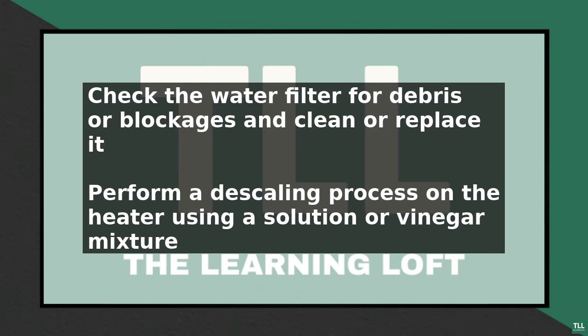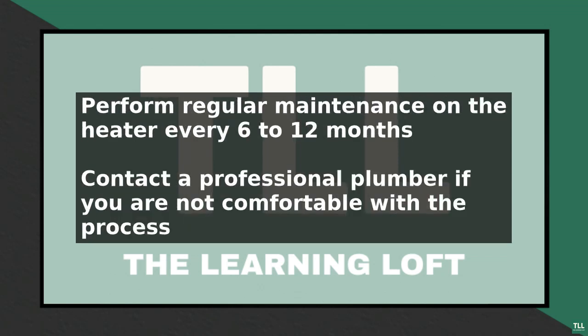It is essential to perform regular maintenance on your Rinnai Tankless water heater to prevent scaling issues. Check the water filter regularly and perform a descaling process every 6 to 12 months, depending on the water quality in your area. By following these steps, you can fix error code 15 and ensure the heater continues to run efficiently.